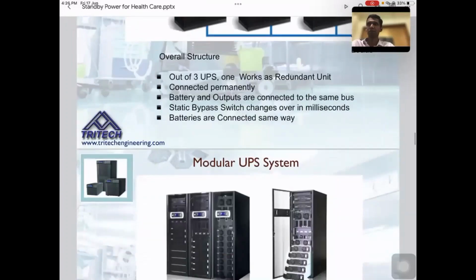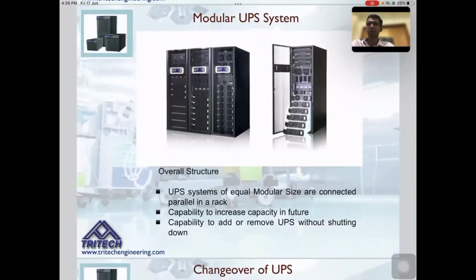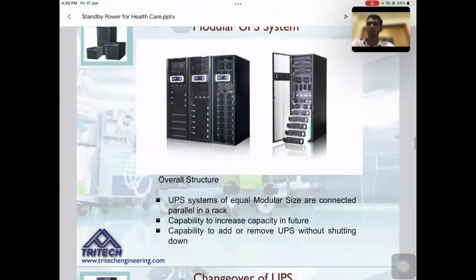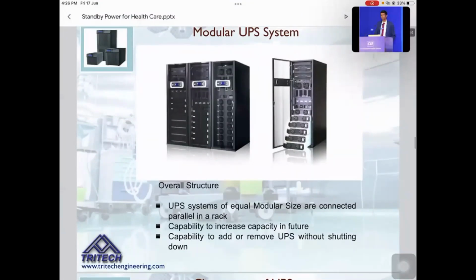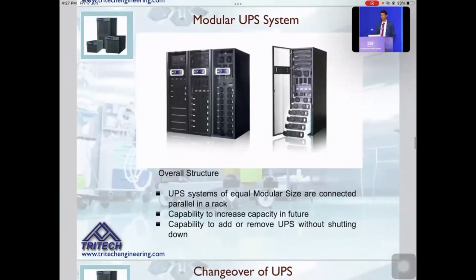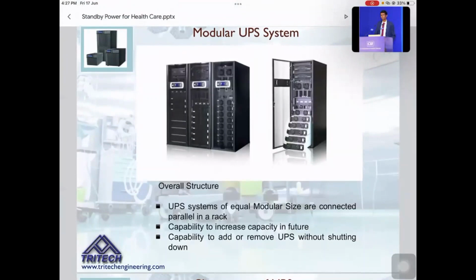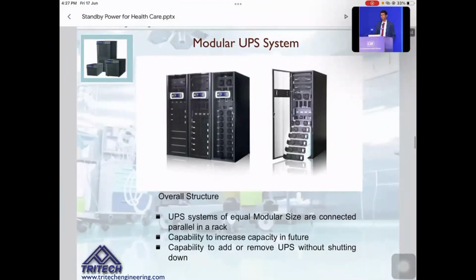If you look at a modular UPS system, how it works is that you have a modular, rack mounted system. Many of these systems are available as one standard unit, which can be paralleled, and you can increase the capacity later also. In the case of a modular UPS, the advantage is you have the capability to increase the capacity in future. We have the capability to replace a unit in the future, and the net cost may not be much higher. And the benefit is also the higher efficiency.